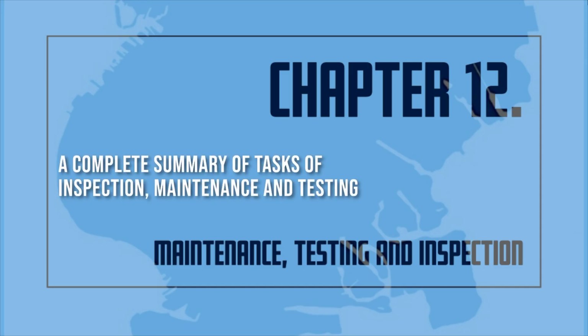A complete summary of tasks of inspection, maintenance, and testing. 1. Inspection. A. Sprinkler systems. Gauges. Dry, pre-action, and deluge systems shall be inspected weekly to ensure that normal air and water pressures are maintained. Where air pressure supervision is connected to a constantly attended location, gauges shall be inspected monthly. Wet pipe sprinkler systems shall be inspected monthly to ensure good condition and that normal water supply pressures are being maintained.